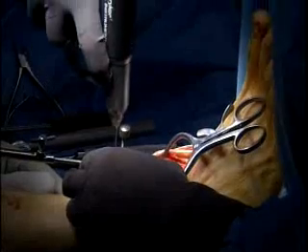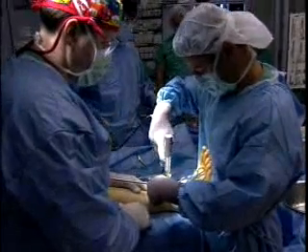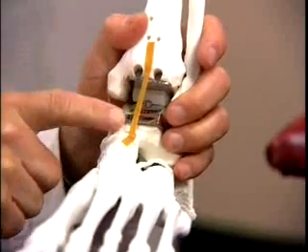Another important and advanced feature of the new implant is its durability. The big thing when replacing joints is that we are putting artificial mechanical parts into the human body, and everything is about wear and friction. The ankle sits at the end of the body, so all of your body weight is concentrated on a very small block — contact forces are huge. We've got to make sure the material can withstand that kind of weight on an ongoing basis, step after step, every day.